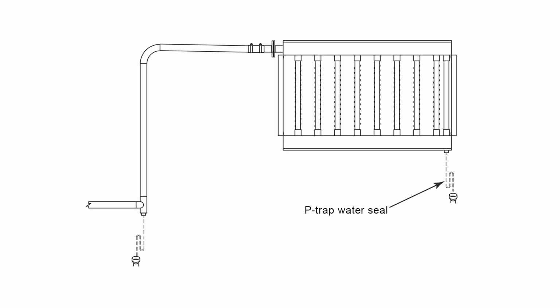And so the moisture management and those safeties are key pieces. And if you want to do a steam generator, if you're worried about that and it's over some sensitive piece of equipment, put a drain pan under it. You're protecting. Sure, there's water in that tank. But in a dispersion system, the water is being managed going down the drain. As long as that header's pitched and the water seal's there, which is what you'd use to cause the steam to go out the tubelets and not out the bottom of the drain, if that can freely flow, you don't have any water in that dispersion system.